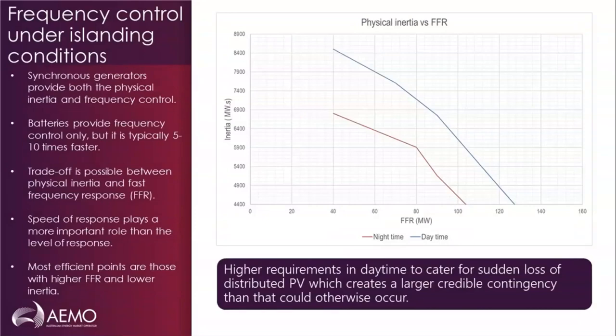On how to manage the frequency under these extended islanding conditions, we use detailed power system modeling and simulation. Primarily, it was based on EMT modeling, considering that extended islanding condition means that the system strength and to some extent inertia would decline. We wanted to make sure that we achieve the most accurate results, because the margin of error under such a small and islanded case is very little.